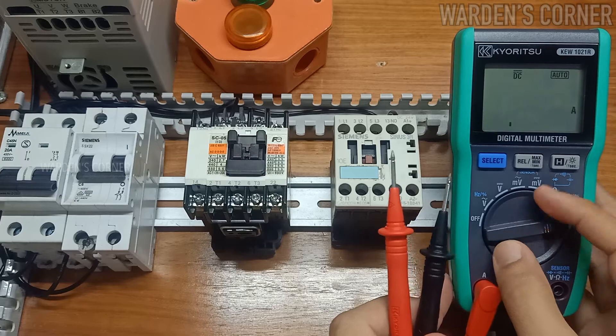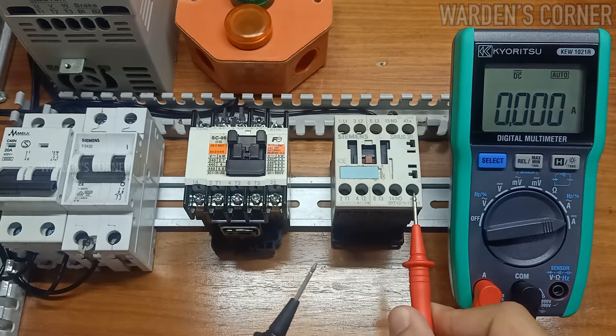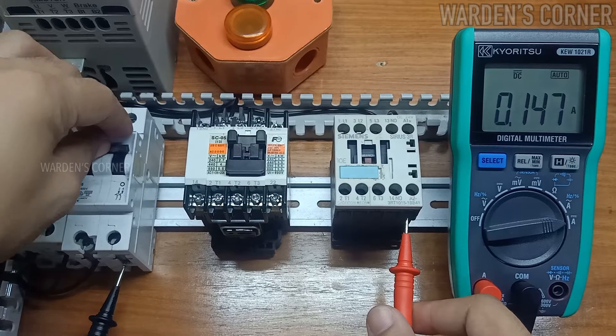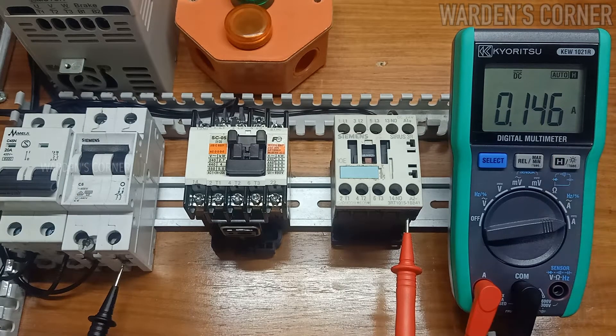As for DC current measurement, our test leads will be connected between the A2 terminal of the 24-volt DC coil magnetic contactor and line 2 of the main supply voltage. Switch on the circuit breaker — 0.146 amperes or 146 milliamps is displayed on the LCD.